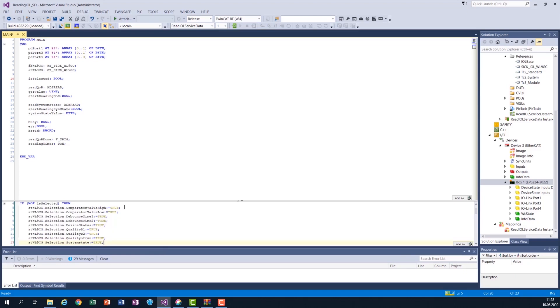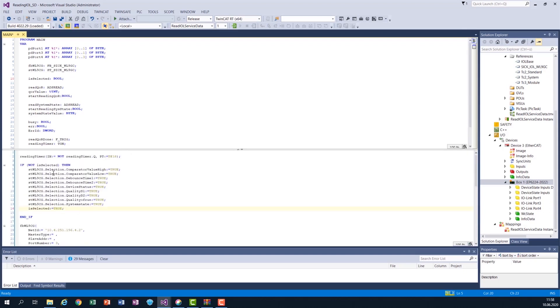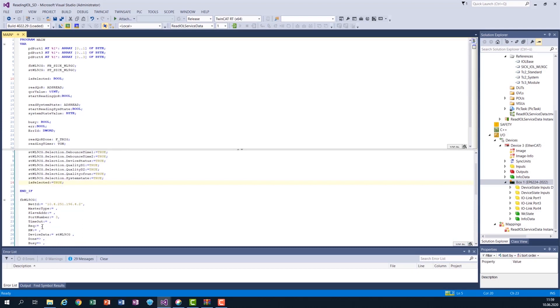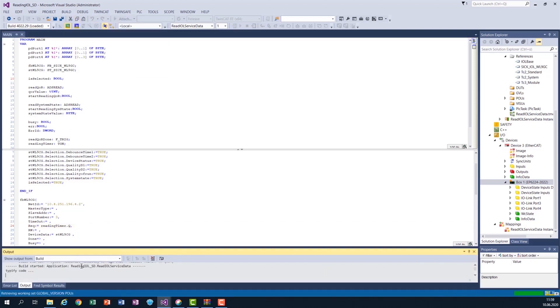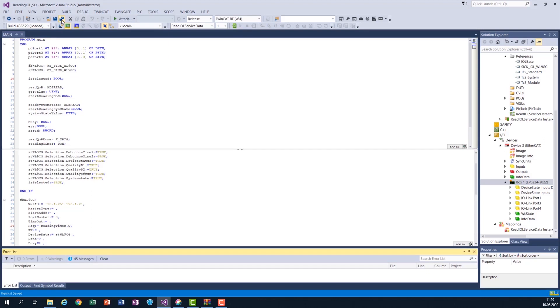Now that we have done the selection, we set is_selected to true so the selection only runs once — we don't need the PLC program going through that code repeatedly. We have selected some variables and will read them automatically, so we trigger the read using the timer we already prepared — reading timer queue. We build to verify everything is okay, get no errors, save it, and we are done.